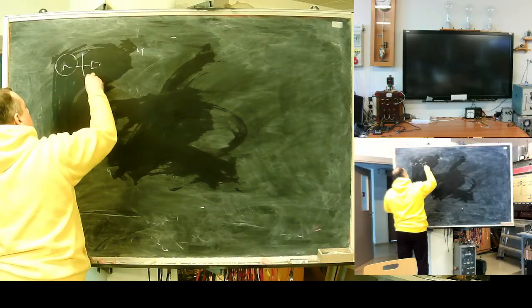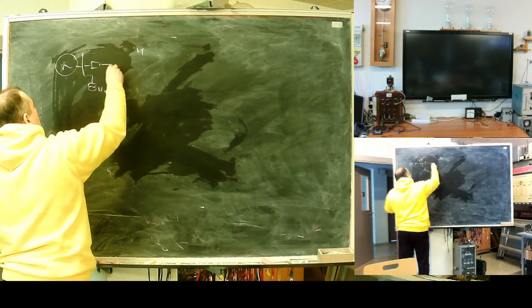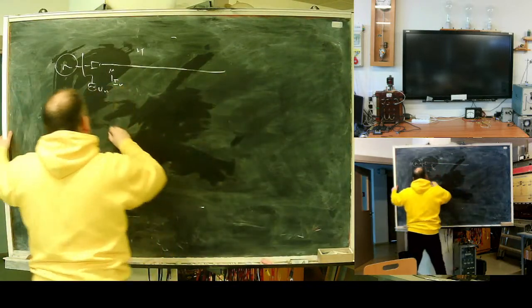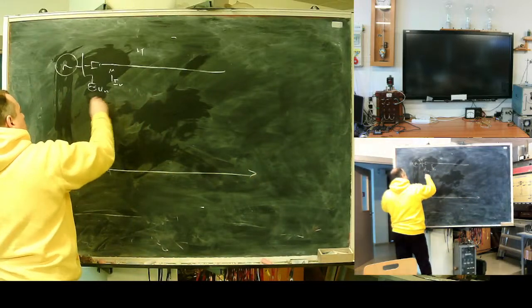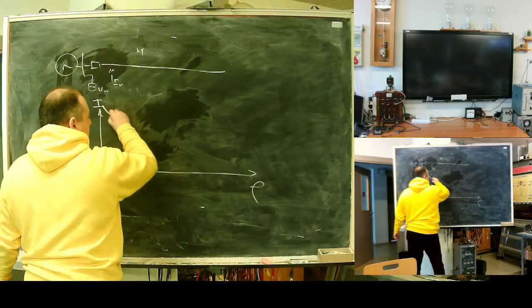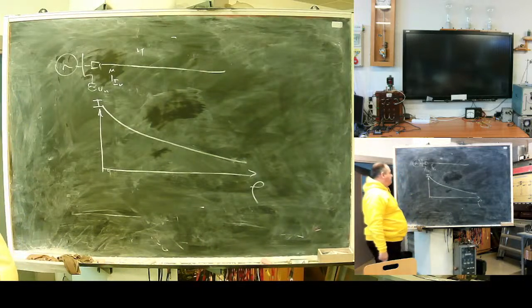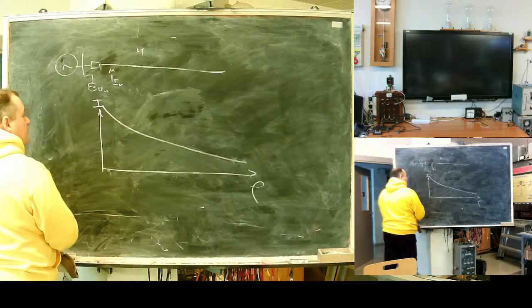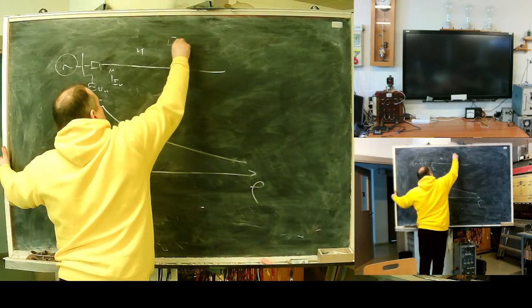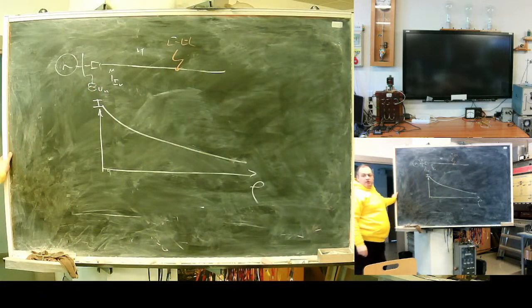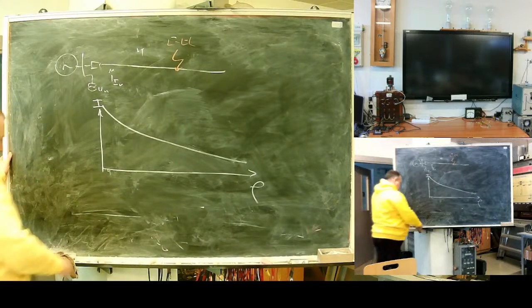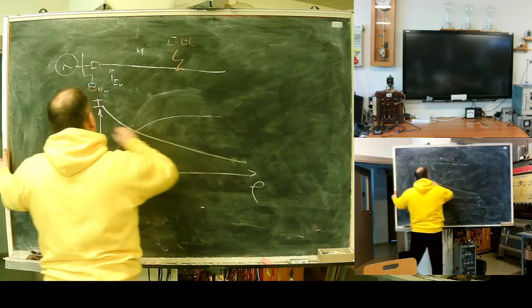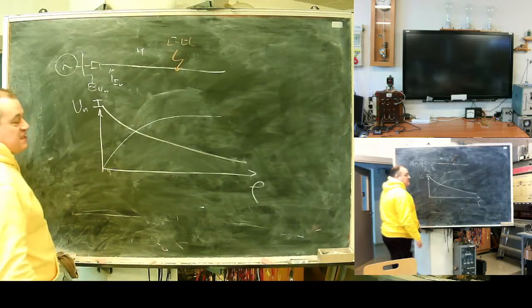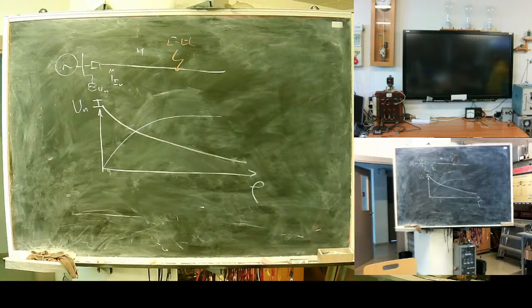Source. Relay. Relay. Current as a function of distance goes like this. What will be the voltage? Let's assume we have a line, three-phase fault. What will be the voltage? Mirror of current. Voltage at a distance 0, in case of three-phase fault, we will get voltage 0.